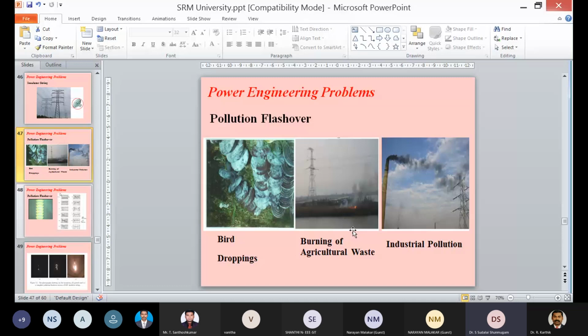I have just given a few examples: bird droppings, burning of agricultural waste, and industrial pollution. One of the significant things which is not shown here is marine pollution. As you know, near the seashore, the air itself contains salt. If the transmission line is passing near the seashore, the salt tends to accumulate on the insulator surface. In the morning and evening, the salt will moisten, it will conduct, arcing, and finally pollution flashover.